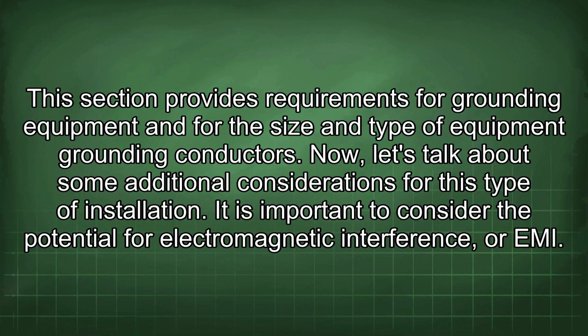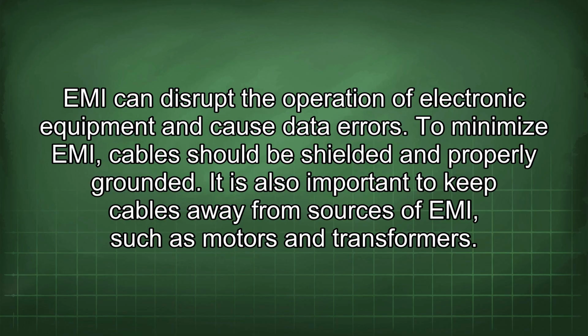Now let's talk about some additional considerations for this type of installation. It is important to consider the potential for electromagnetic interference, or EMI. EMI can disrupt the operation of electronic equipment and cause data errors. To minimize EMI, cables should be shielded and properly grounded. It is also important to keep cables away from sources of EMI, such as motors and transformers.